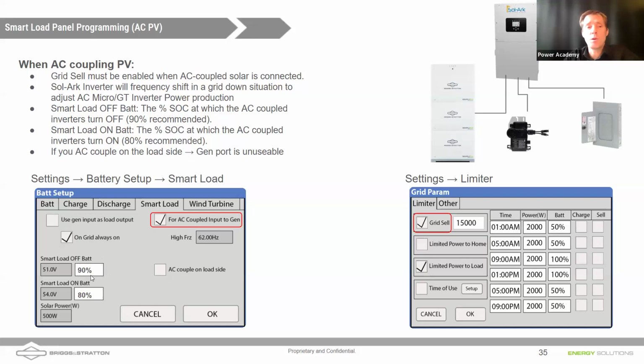Yeah, and AC coupled solar, I mean, its job is to pump out as much electricity as it can, and essentially, it's kind of dumb, right? There's not a whole lot to an AC coupled system because it's not designed for backup, right? But with a Sol-Ark, the Sol-Ark is going to be able to turn that AC coupled solar off to prevent overcharging that battery, and we do that by putting this setting here. The 80% threshold is like before. We don't want the AC coupled solar turning on and off right at 90%. So we have a slight discrepancy there. And it says, well, let the batteries discharge until they hit 80%. And once they hit 80%, turn that AC coupled solar back on and top them off again.